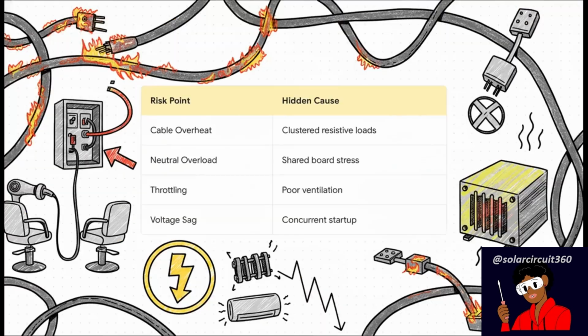physical environment. Let's slow down for a second and bring our focus back to the physical safety of the building, because these are the silent, incredibly dangerous failure points that happen in real physical spaces when you ignore these rules and just blindly trust a spreadsheet. If you ignore airflow and thermal stress, here's what actually happens. First, you get cable overheating from clustered resistive loads. We're talking about those thick cable bundles running right under the salon chairs.